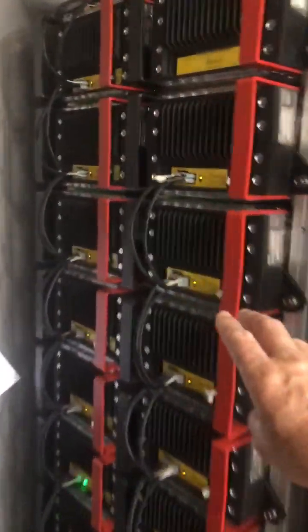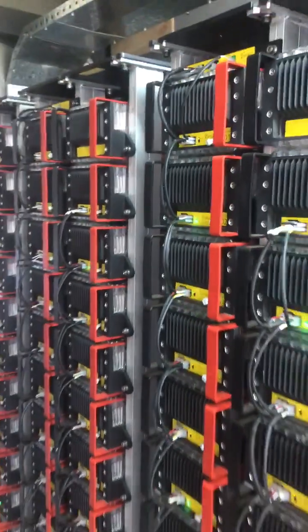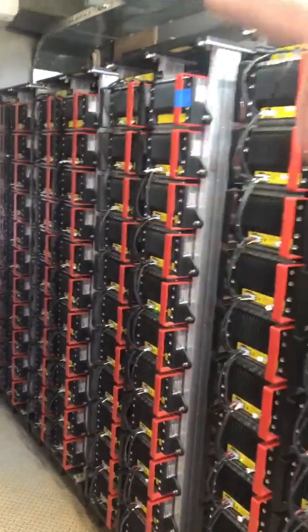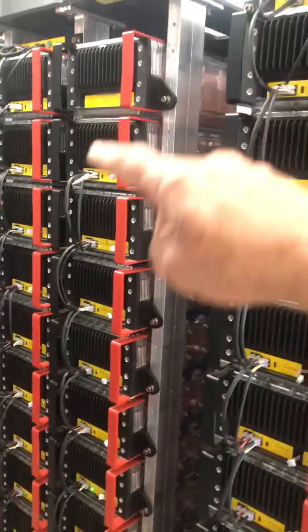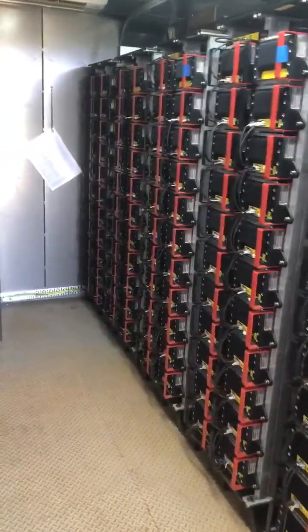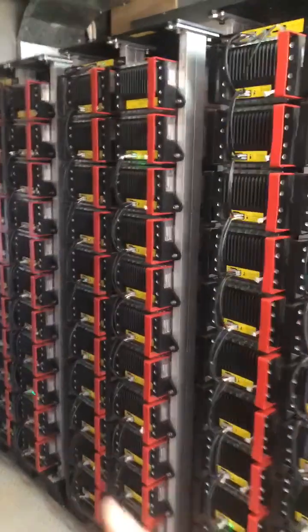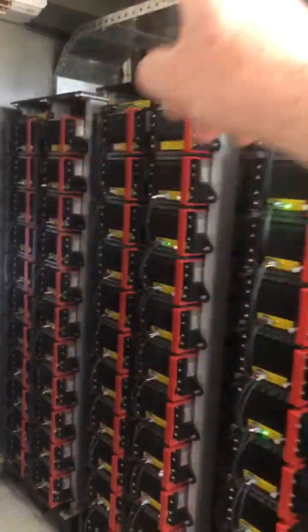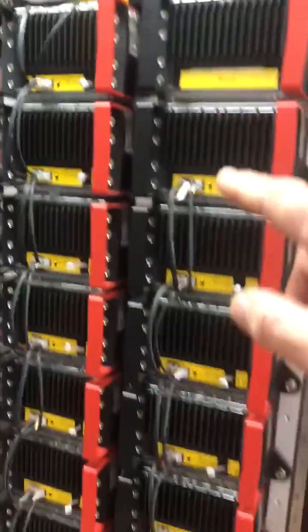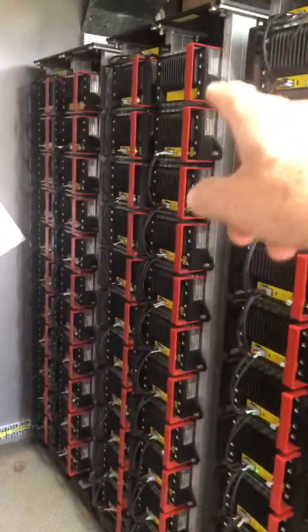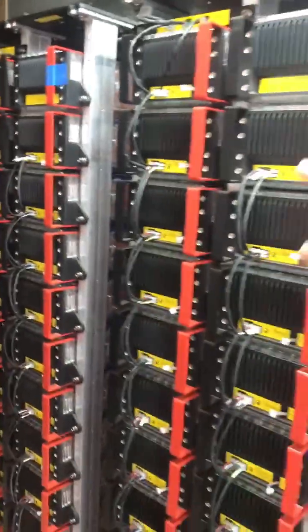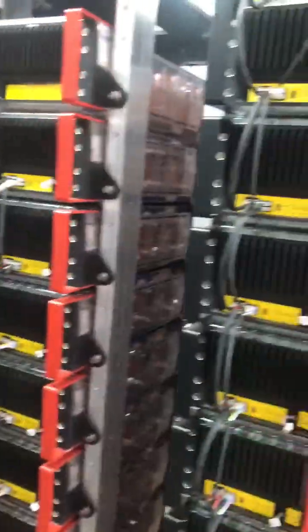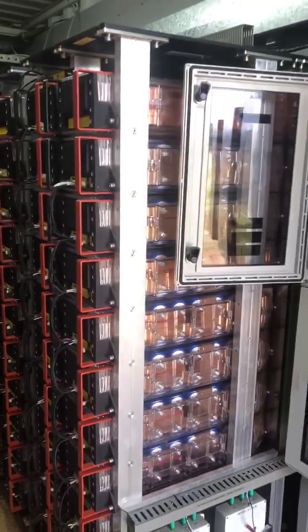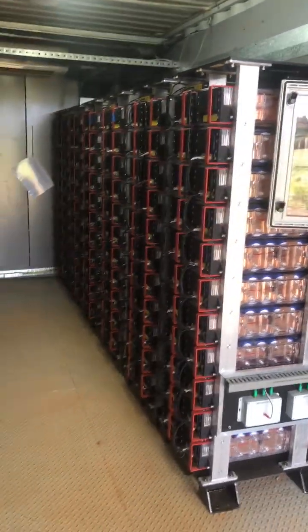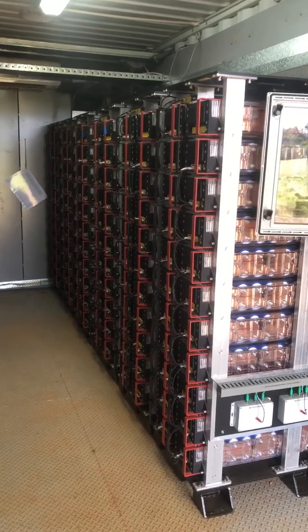So what we did was we brought the cabling to the first battery, then we skipped to the third battery stack, and then we skipped to the fourth battery stack. In other words, we ended up with battery stack A loops to A, which loops to A, and battery stack B, which is the second stack, loops to B, which then loops to B. And so that was just a clever way to keep the cables all the same length.